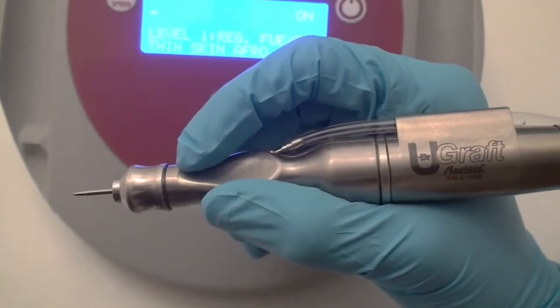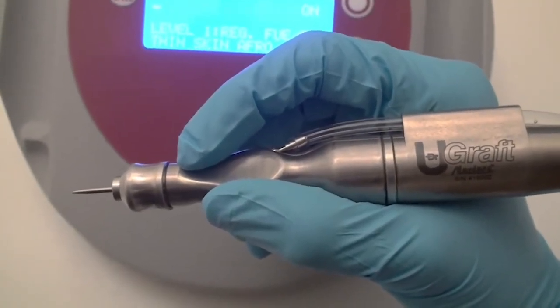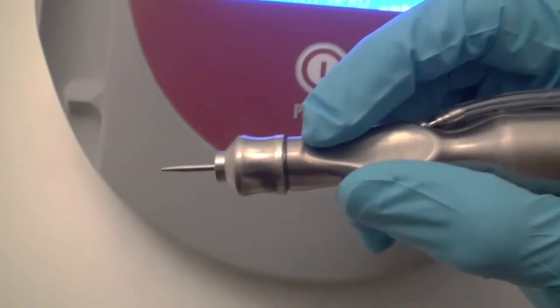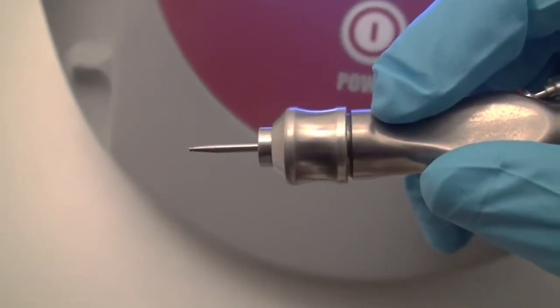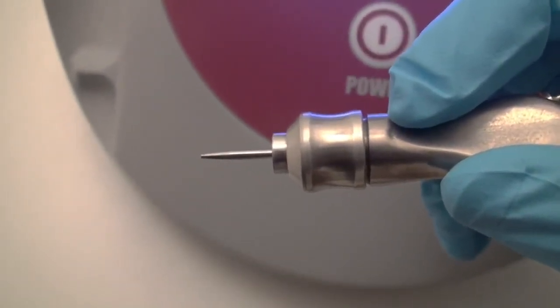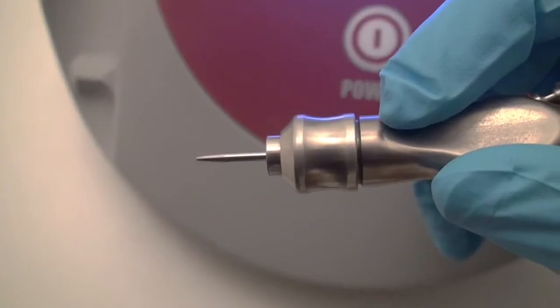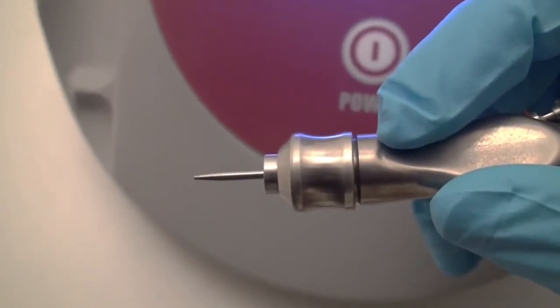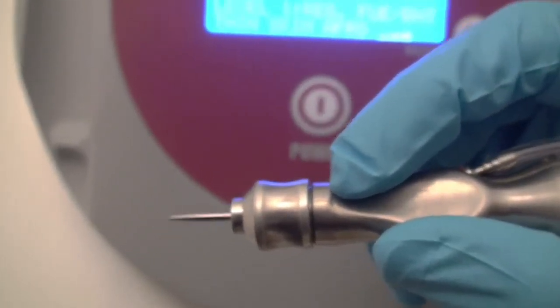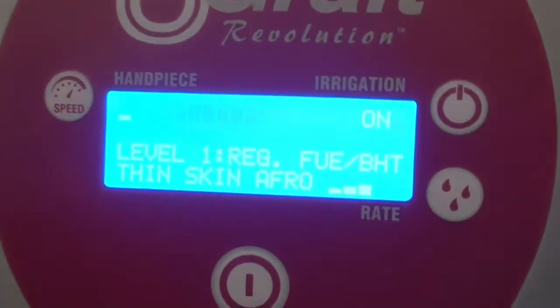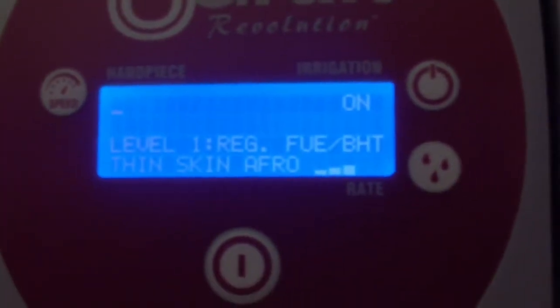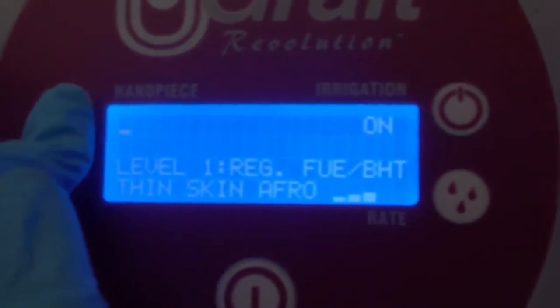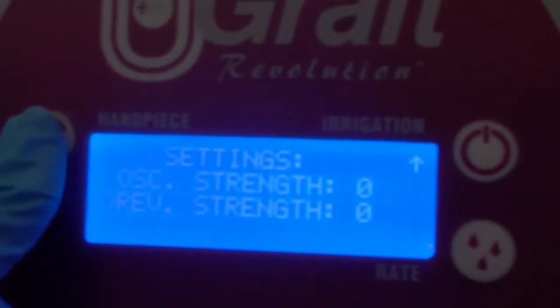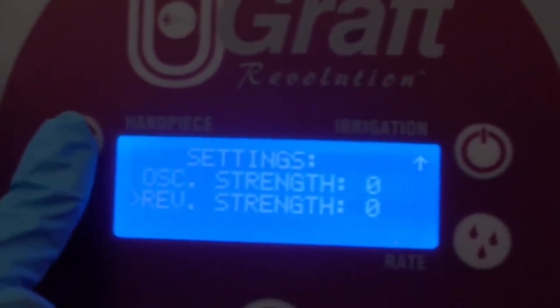When the handpiece does not rotate smoothly, or altogether, it may indicate the need to adjust the strength of the handpiece rotation. Failure to rotate smoothly is when the handpiece stutters like this. To fix this, adjust the rotation strength by pressing the speed button on the left for 2 or 3 seconds. The strength settings would appear as shown.